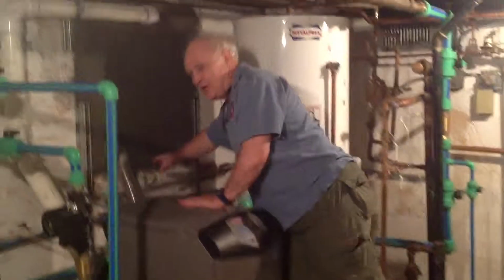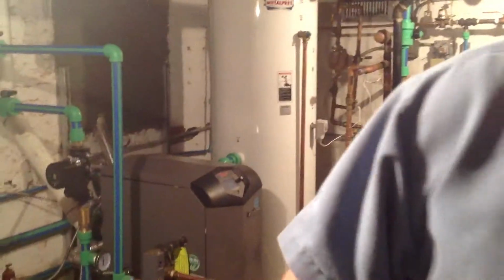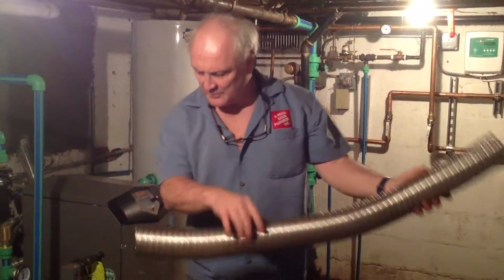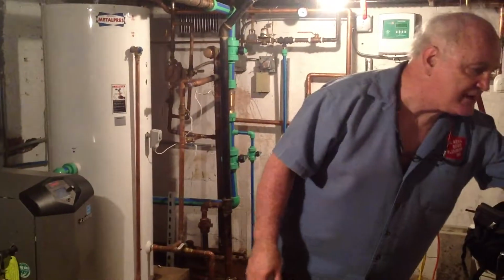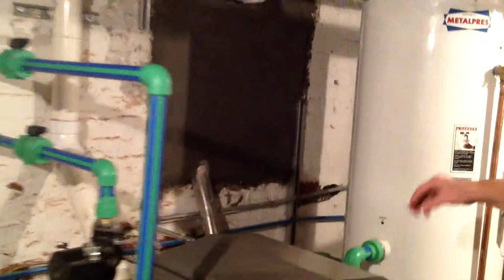And the condensing piping here goes up the chimney. This here is a piece of stainless steel pipe, and that's actually the exhaust. We take that up in a liner. Where's the liner? These are flexible stainless steel liners. It's actually got some rigidity to it. It's really good stuff. We take it up through the hallway to the roof and pull it down through the chimney, and then we cut it off. Then down here in the basement, we make a conversion to single wall stainless steel pipe, and that takes care of the exhaust all the way up the building.